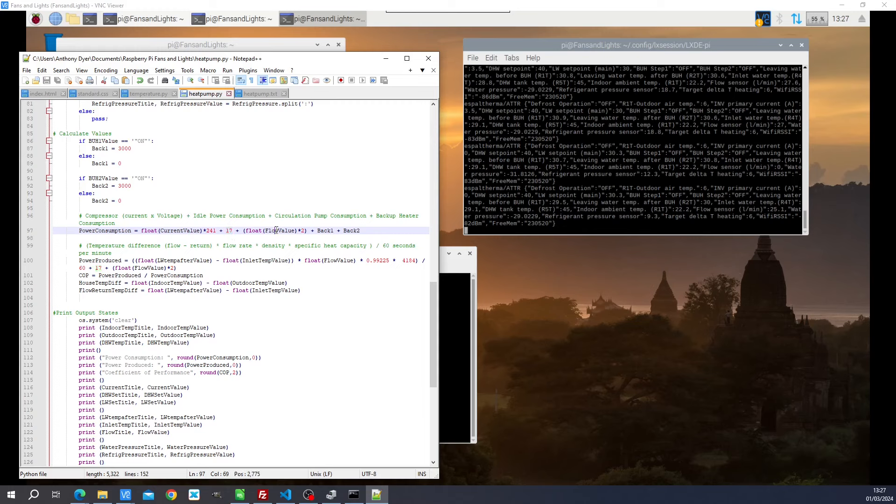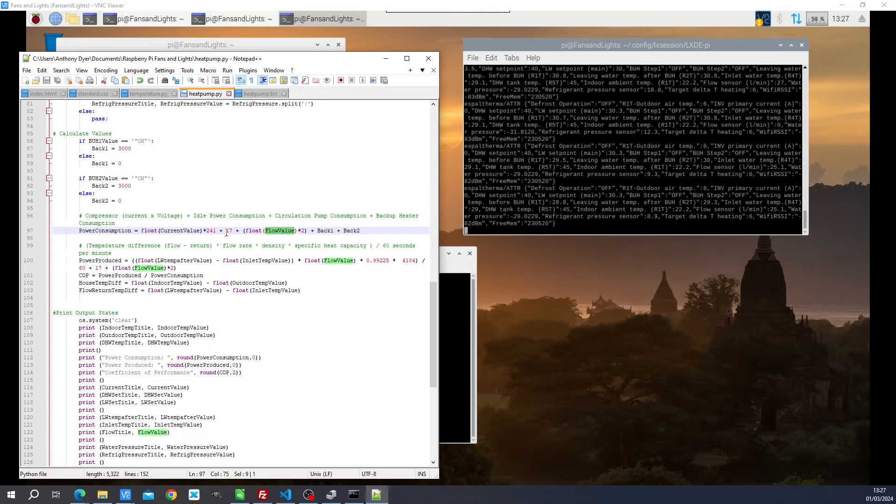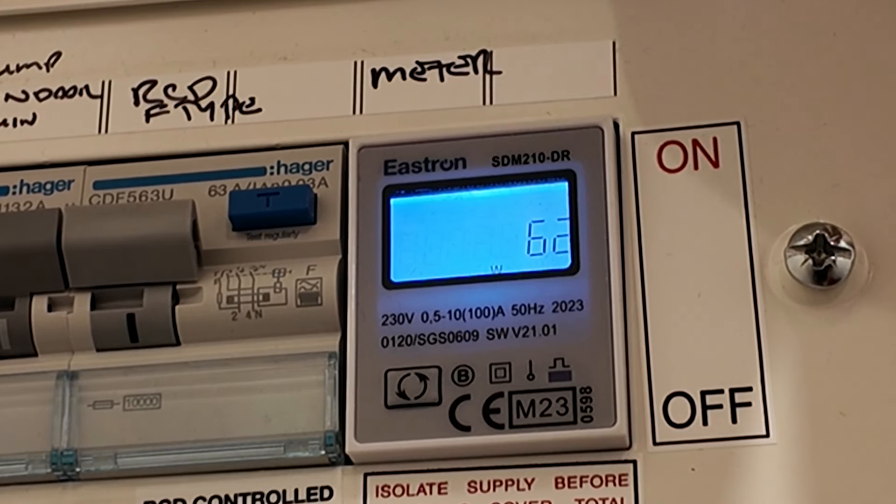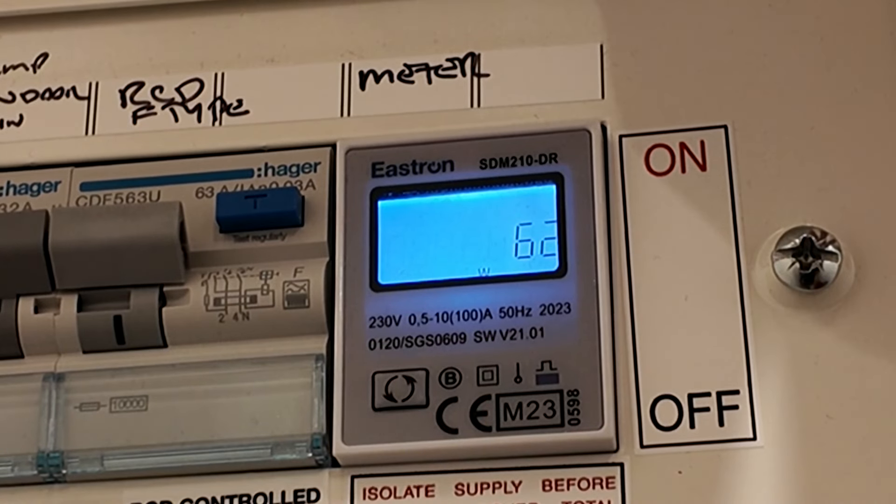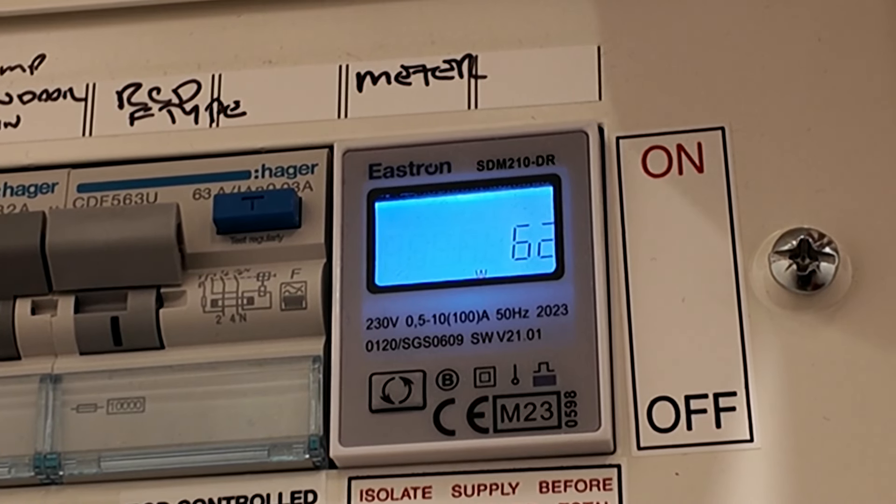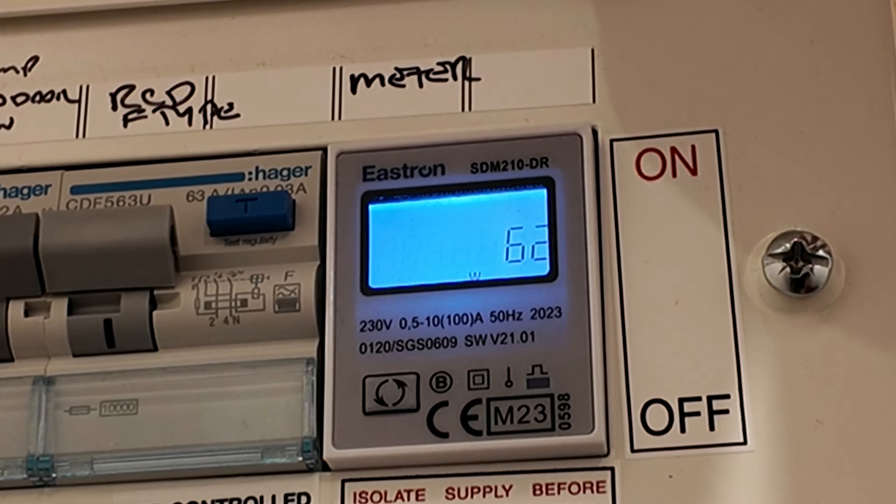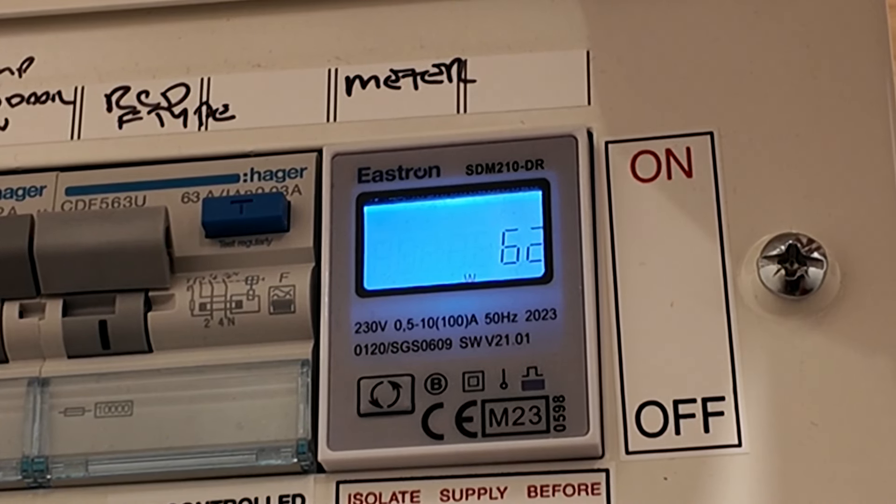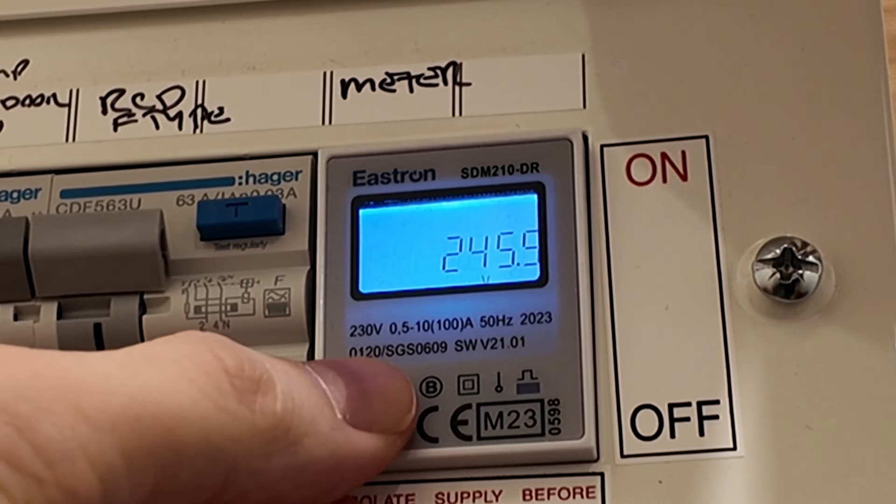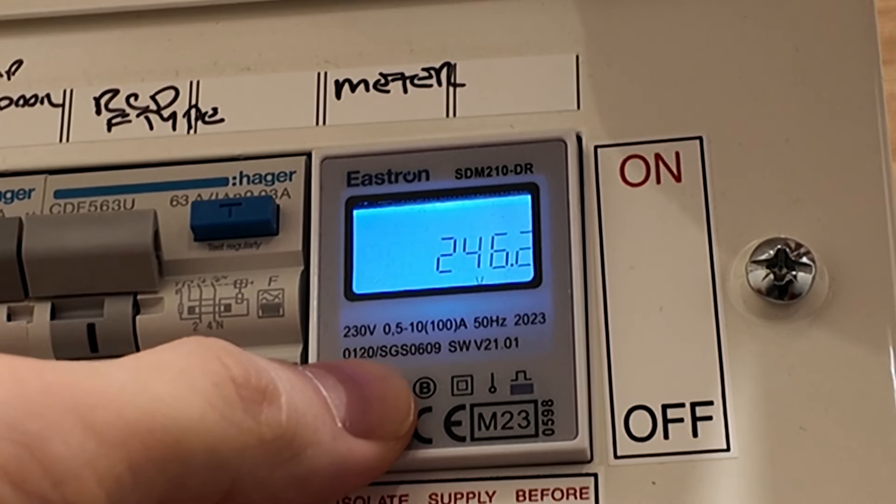So at the maximum speed, you're getting about 25 liters per minute. Multiply that by 2. That's 50 watts plus 17. That's about 65 watts. And the actual power consumption is about 61. So as you can see here, we've got about 62 watts of power being drawn by the system. I can hear the pump is running. When the pump is not running, this will typically drop down to about 17 watts of power. And when the compressor is running, what I find is that there is pretty good correlation between my calculated power consumption and the power consumption shown on this energy meter.